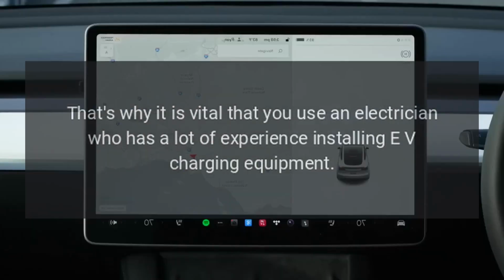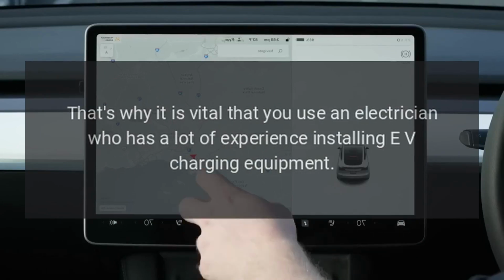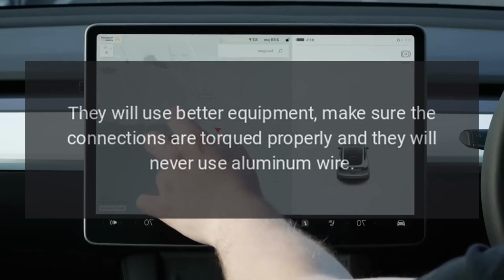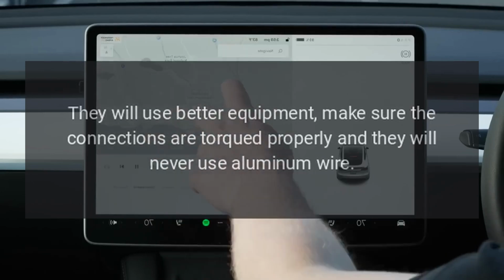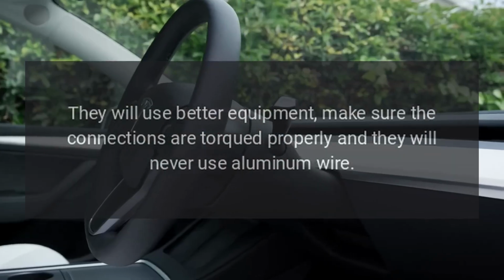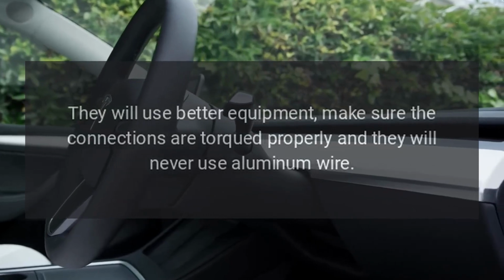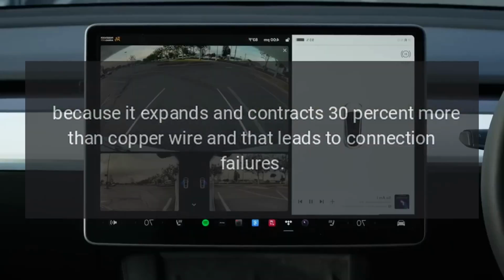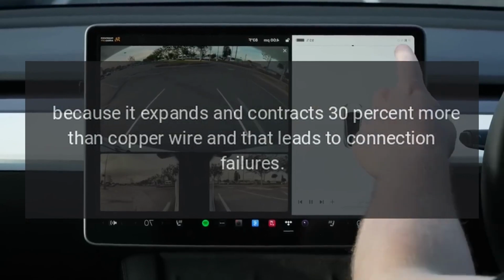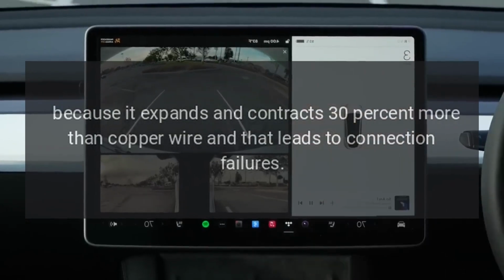That's why it is vital that you use an electrician who has a lot of experience installing EV charging equipment. They will use better equipment, make sure the connections are torqued properly, and they will never use aluminum wire, because it expands and contracts 30% more than copper wire, and that leads to connection failures.